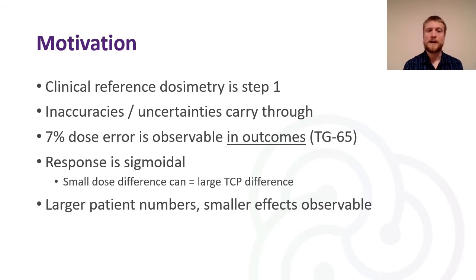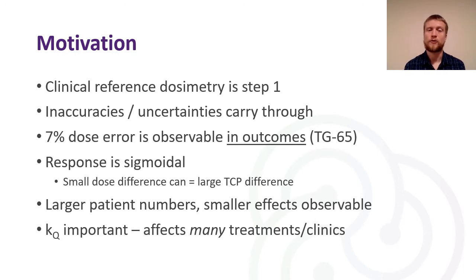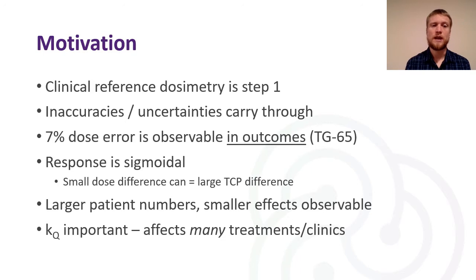When patient numbers increase — so a larger patient cohort — smaller effects can be observable as they become more statistically significant. KQ is important here because it affects many different treatments across many different clinics. Any country that does not have a direct calibration service means that everyone is using the same KQ set from a protocol, and if there's an error in that, it will propagate through to any clinic using that KQ value, resulting in an error or larger uncertainty in their dosimetry. Maximising accuracy here is obviously very important.